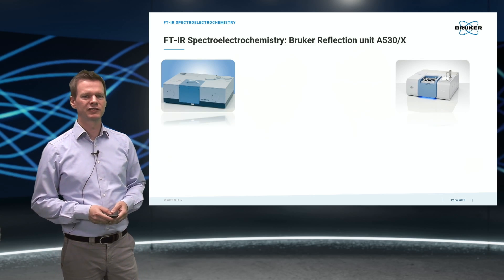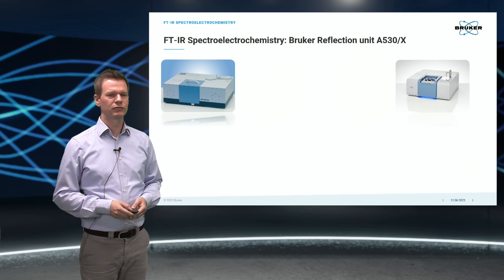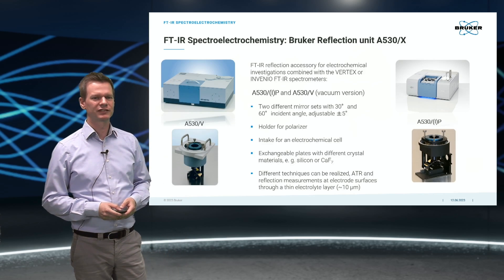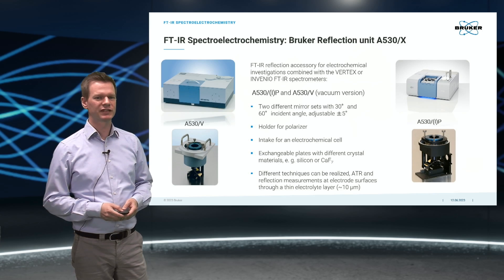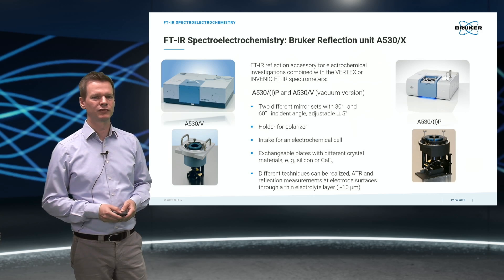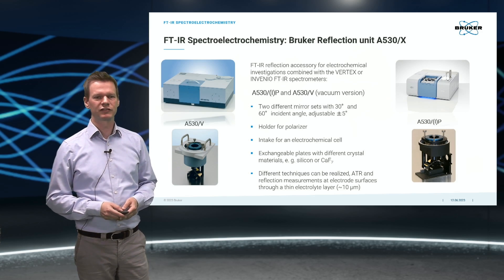At Bruker, we offer for the Vertex and Invenio FTIR spectrometer series a reflection unit for electrochemical experiments. There is one version for the vacuum system and one version for the purge systems. An electrochemical cell can be simply inserted into this reflection unit, then the beam is guided via mirrors at 30 or 60 degrees of incidence to a crystal window plate. This crystal window plate can be exchanged easily, realizing different measurement modes. Additionally, the use of polarized IR light is possible.